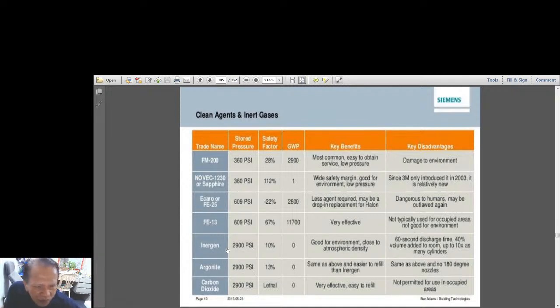Inergen, 2,900 psi, so very, very high pressure. Safety factor is 10. 0 GWP. Good for environment, close to atmospheric density. 60-second discharge time, so 1 minute. 40% volume added to room, up to 10 times as many cylinders. So very bulky. So you need so many cylinders. Okay, that's Inergen. Argonite, same pressure, 13%, same as above, and easier to refill than Inergen.